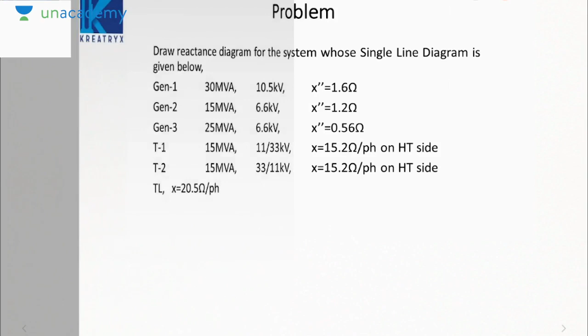So here we have been asked to draw the reactance diagram of the system whose single line diagram is given. Various ratings of the machines are given: generator 1, generator 2, generator 3, T1, T2 and the transmission line. Now the first step that you must do is divide the power system into different sections based on the transformer. So the circuit is shown here. How? Like this. This will be section 1, this will be section 2, this will be section number 3. So I have divided the power system into 3 sections based on the transformer windings.